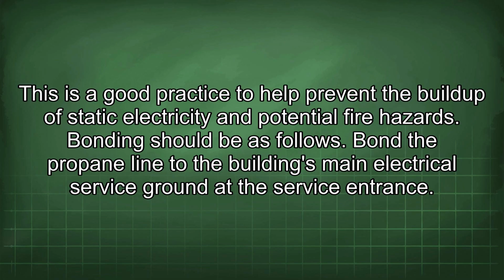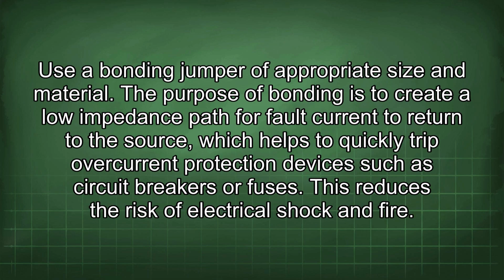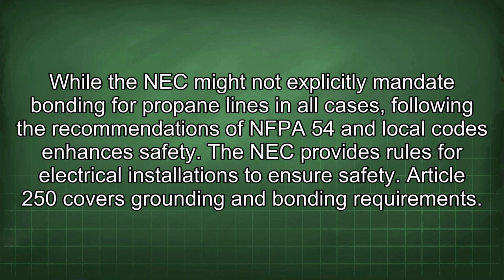Bonding should be as follows. Bond the propane line to the building's main electrical service ground at the service entrance. Use a bonding jumper of appropriate size and material. The purpose of bonding is to create a low impedance path for fault current to return to the source, which helps to quickly trip overcurrent protection devices such as circuit breakers or fuses. This reduces the risk of electrical shock and fire. While the NEC might not explicitly mandate bonding for propane lines in all cases, following the recommendations of NFPA 54 and local codes enhances safety.